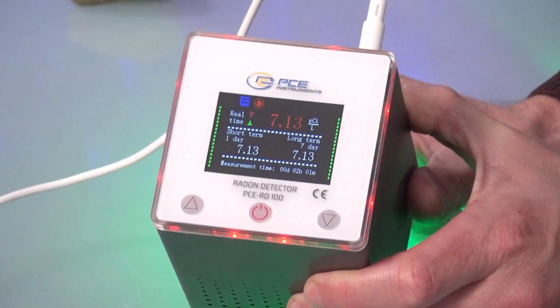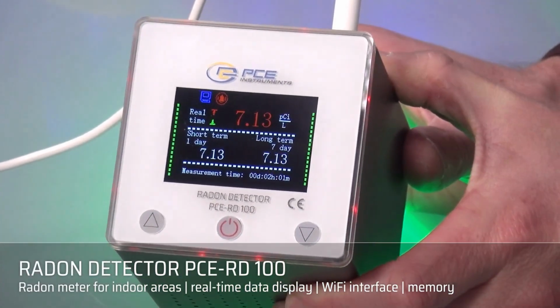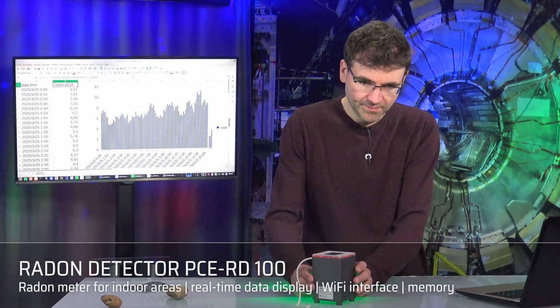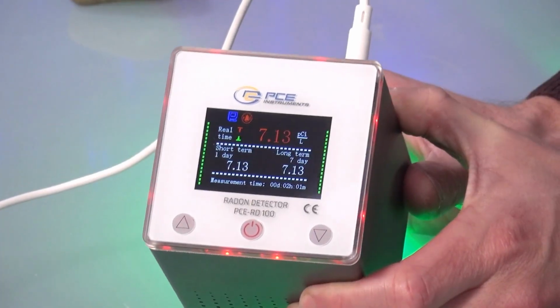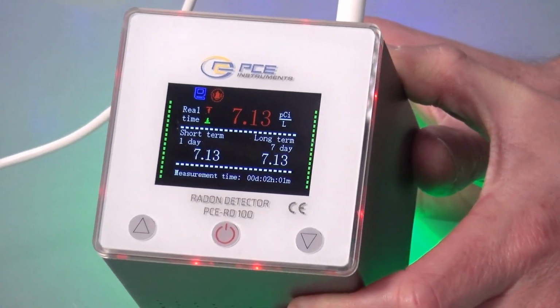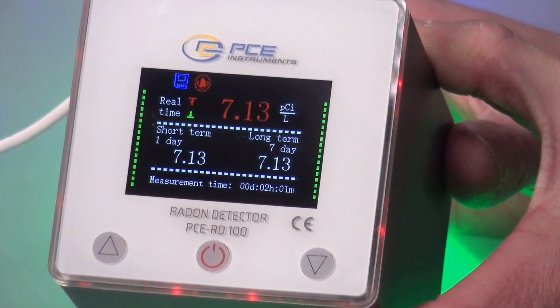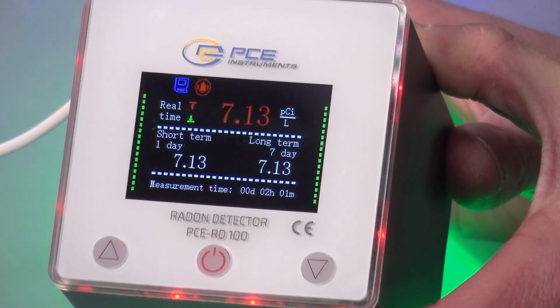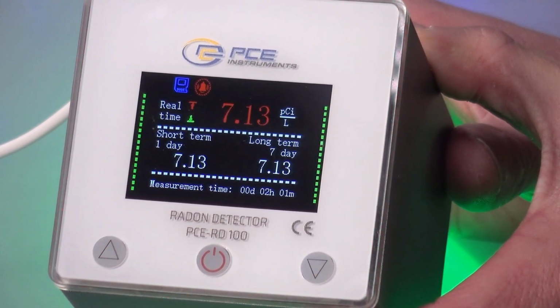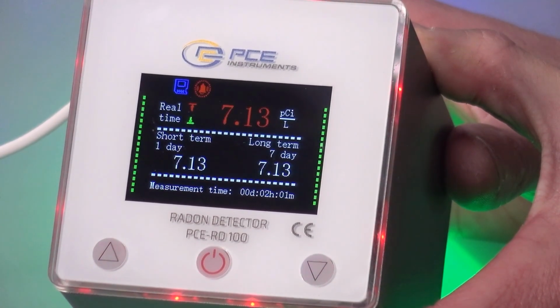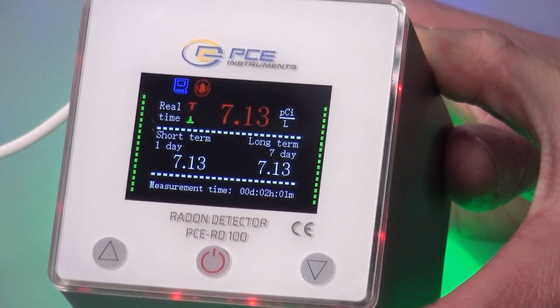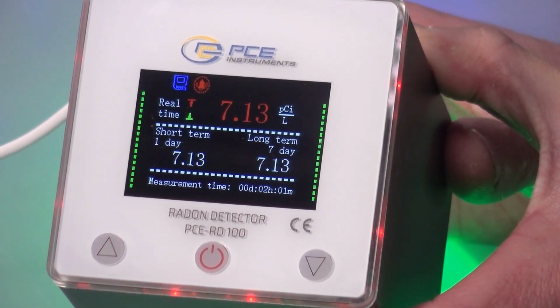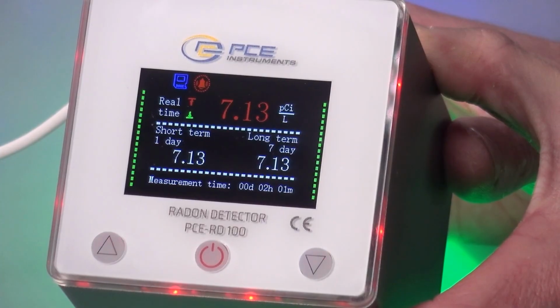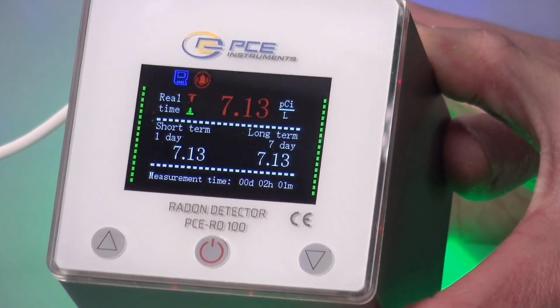Hello and welcome. I would like to introduce you to the PCE-RD 100, a radon detector, a tabletop device you could say, with a display on top. And we see on the display, it's a very clear display, we see the most important value in large, namely the radon concentration that this device measures. It works with a pulsed ionization chamber and can measure values between 0.1 and 99.9 picocurie per liter, and is therefore suitable for the entire common range of radon concentration.